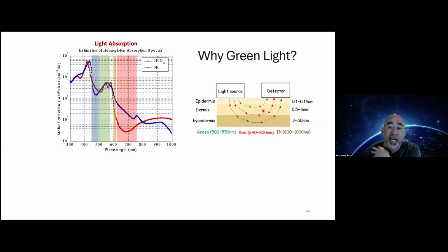And this leads to less consumption of LED light or power, and is also less prone to motion artifact, because the more you move, the more likely that you're going to have the underlying tissue move, and as a result, sort of affecting the results. And this might explain why when you have the pulse oximeter light on, or the red light on, it requires a higher intensity and therefore drains the battery much more than the green light.